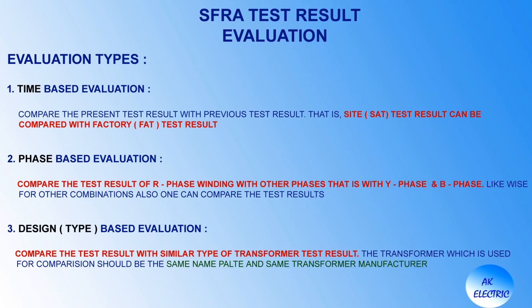SFRA test result evaluation can be done by three types: time-based evaluation, phase-based evaluation, and design-based evaluation. Time-based evaluation compares the present test result with a previous test result — for example, site test result compared with factory test result. Phase-based evaluation compares the test result of R-phase winding with other phases — Y-phase and blue-phase — and other combinations. Design-based evaluation compares the test result with a similar type of transformer, which must have the same nameplate ratings and same manufacturer.